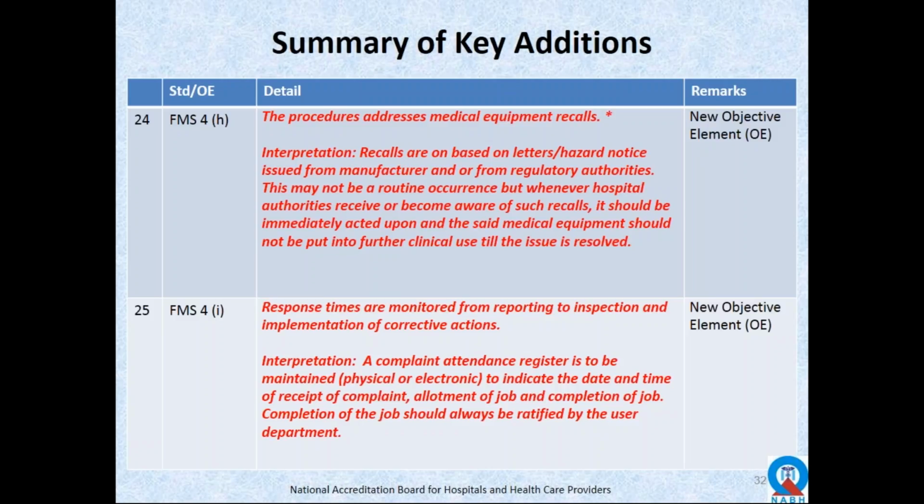FMS 4I, another new objective element which is now added for the medical equipment. In the third edition, it was added in the standard on general engineering equipment. It is now also added to the medical equipment, because here also the response times monitoring is very important, and the response time should be monitored from reporting to inspection to the implementation of corrective action. So we need to have a register, a complaint attendance register, which is maintained either physically or electronically, which indicates the time of complaint, the time of allotment of the job, the time of attendance of the job, and the time at which the job is completed.